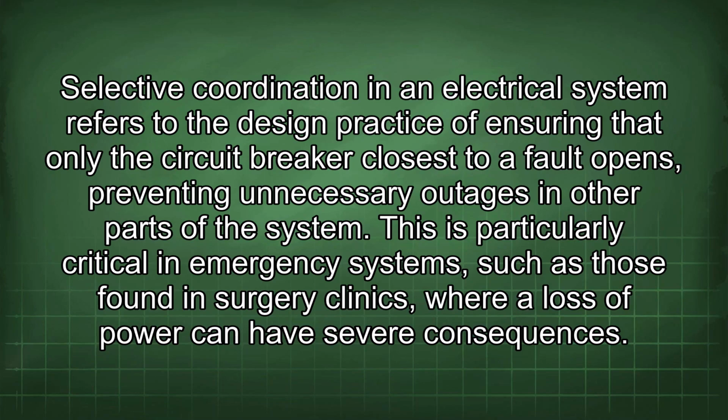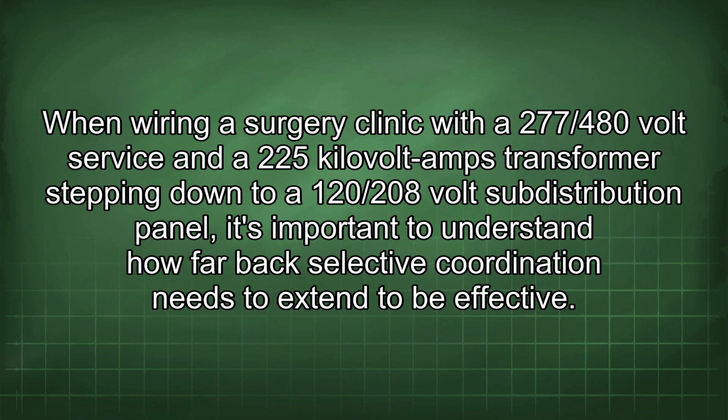Selective coordination in an electrical system refers to the design practice of ensuring that only the circuit breaker closest to a fault opens, preventing unnecessary outages in other parts of the system. This is particularly critical in emergency systems, such as those found in surgery clinics, where a loss of power can have severe consequences.